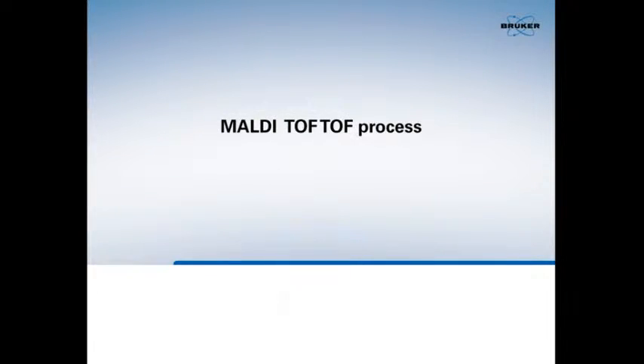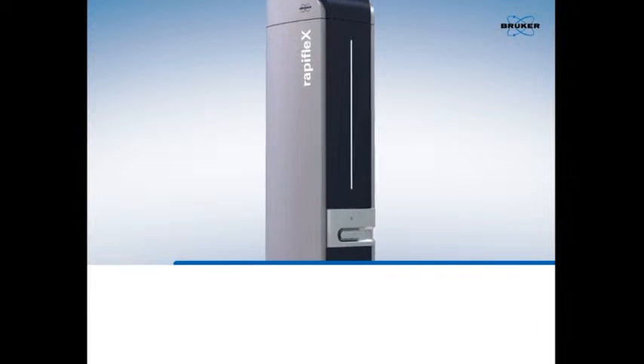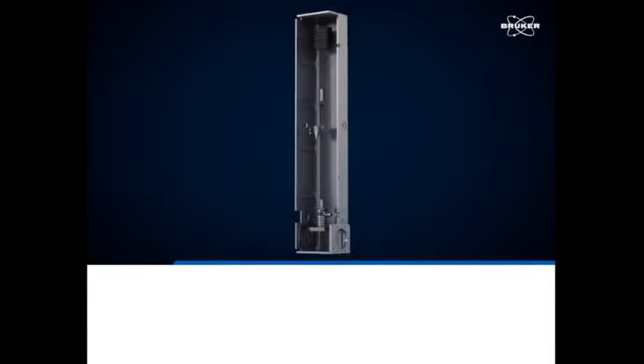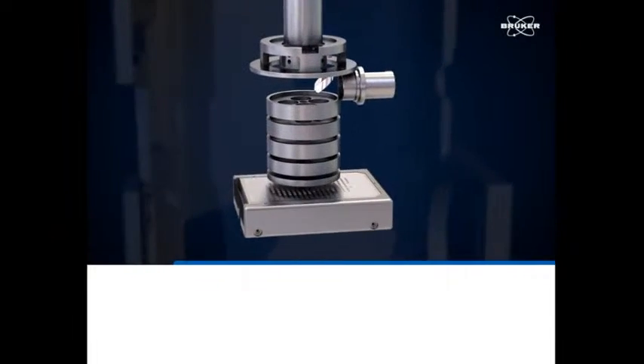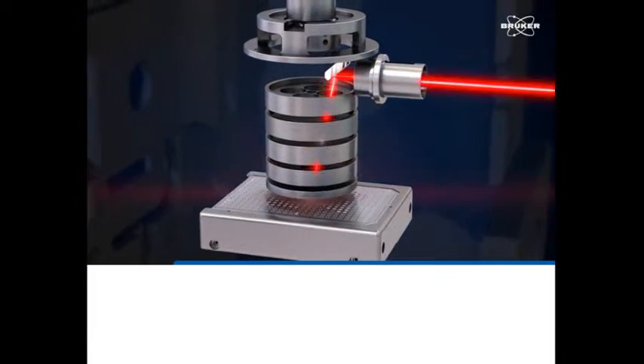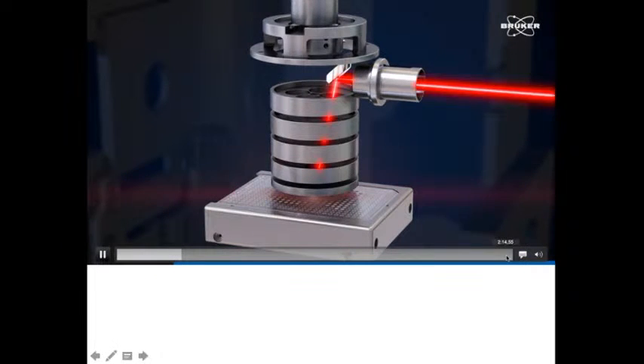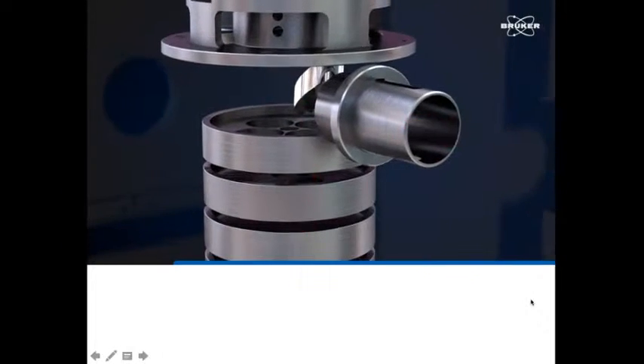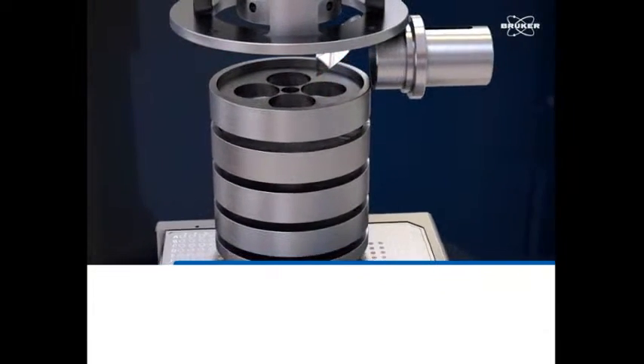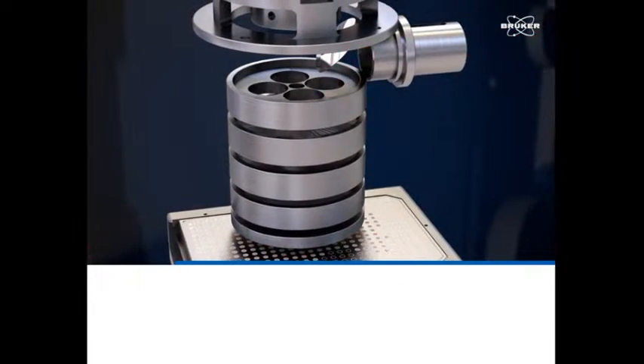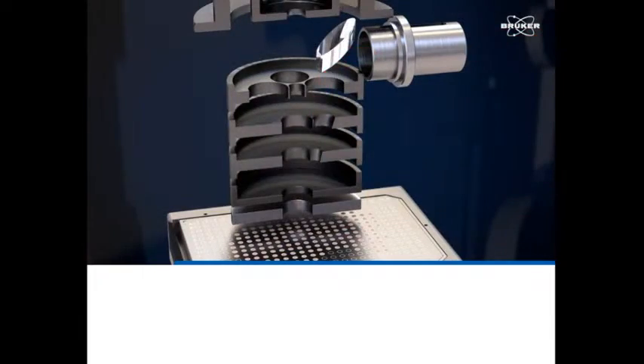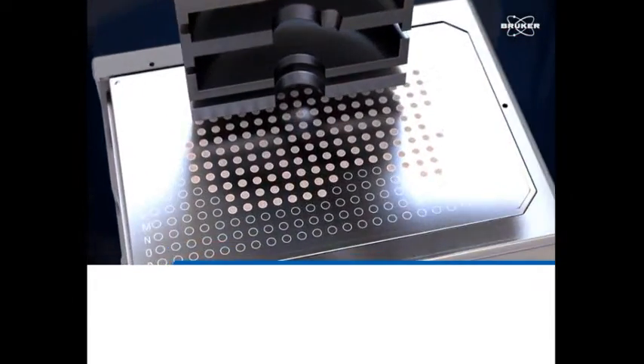MALDI-TOF/TOF process. MALDI-TOF/TOF analysis provides additional structural information for target molecules, as MALDI-TOF/TOF is a two-phase process. Fragmentation can occur by application of higher laser energies, known as LID, laser-induced dissociation, or a background gas can be introduced to promote ion collisions. This process is known as collision-induced dissociation, or CID.